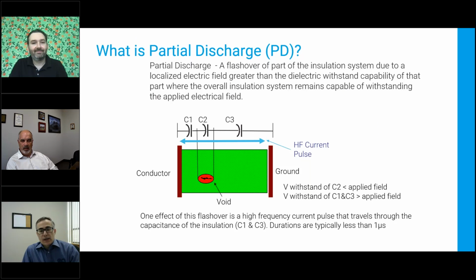What's really going on is that if you use this little diagram that we have here, you see there's this green part which represents the insulation, and we have an air bubble inside, or it could be just under the surface or on the surface. It's the same effect, and you have an air gap there. And in an overall health type of instrument, maybe like a megger or something, you go for a cable, you might not pick this up, or a thermal camera, since it's internal, might not generate enough heat.